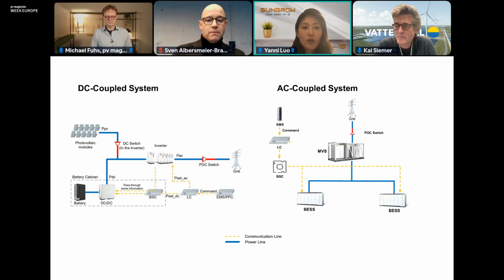During the daytime, when the PV connection is on, there are several modes: the PV part can charge the battery and charge into the grid at the same time, the PV part can charge into the grid individually, or the ESS part can charge into the grid individually. For this mode, the control logic is more complicated, and project developers need to do more revenue analysis to see if it makes sense from a financial and device perspective.